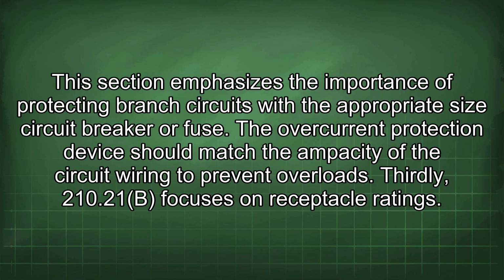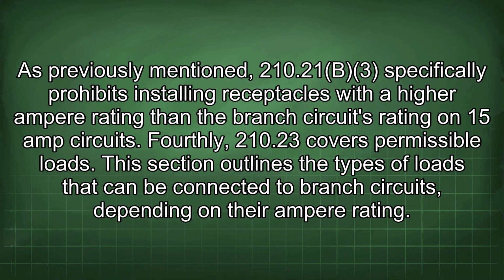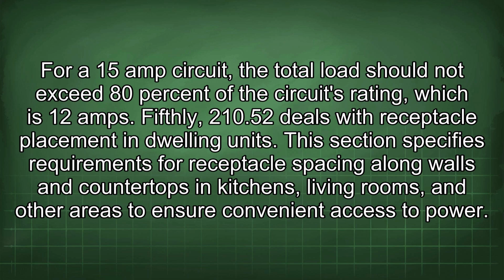Thirdly, 210.21(B) focuses on receptacle ratings. As previously mentioned, 210.21(B)(3) specifically prohibits installing receptacles with a higher ampere rating than the branch circuit's rating on 15 amp circuits. Fourthly, 210.23 covers permissible loads. This section outlines the types of loads that can be connected to branch circuits, depending on their ampere rating. For a 15 amp circuit, the total load should not exceed 80% of the circuit's rating, which is 12 amps.